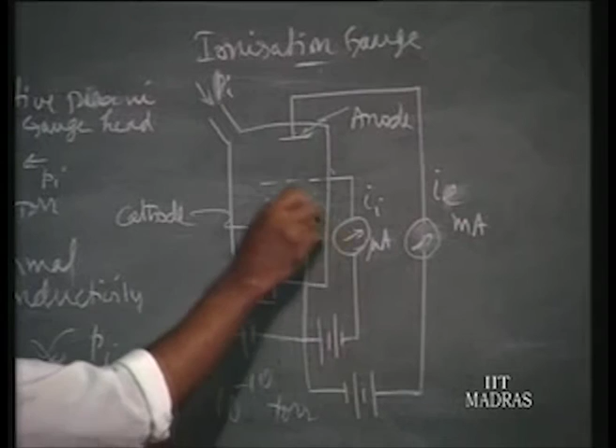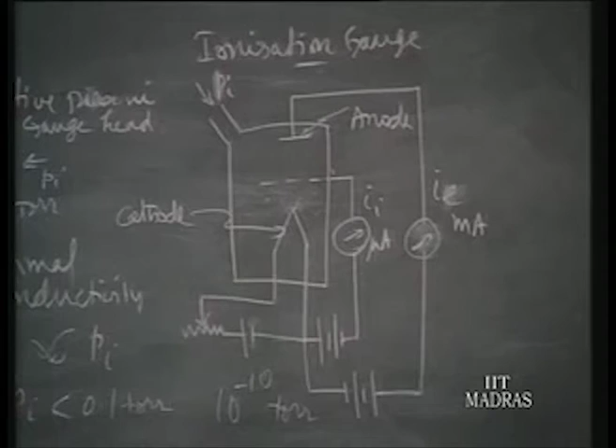So that, in other terms, indicates the vacuum pressure. More pressure means more molecules come here, so that's why it indicates the vacuum pressure. The ammeter in the grid circuit is calibrated in terms of the vacuum pressure. When the pressure falls, there are fewer molecules, and less current will flow here. That means vacuum is more. Like that, it is calibrated, and it can go up to 10 to the power minus 10 torr. Its sensitivity is up to that.